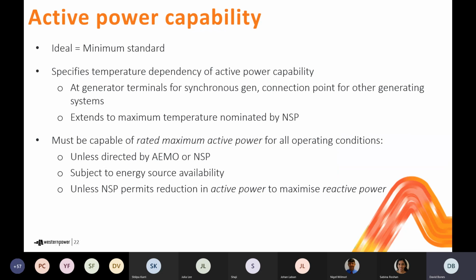So let's get started on the first of the requirements, which is the active power capability. So the active power capability generator performance standard defines the requirement for the generating system to be able to deliver its rated active power output under all conditions. The GPS provides clarity around what's meant by all conditions. And there's a requirement that the GPS include information about any reduction in active power capability with ambient temperature. Further, the GPS requires that the rated maximum output capability needs to be able to be specified at the generator terminal levels for synchronous generating units or at the connection point for other generating systems.